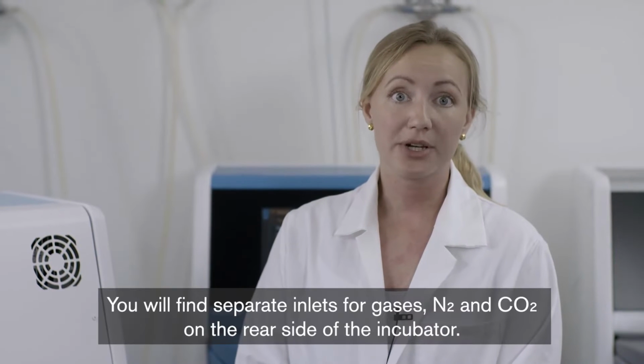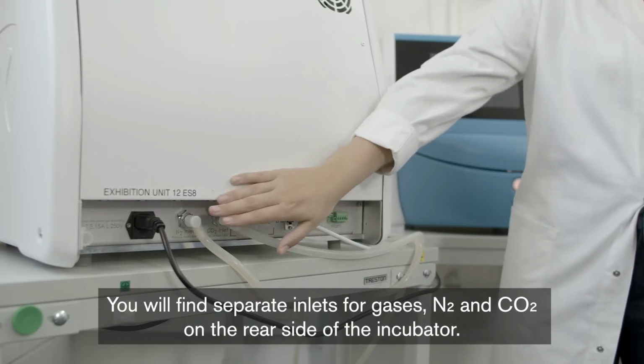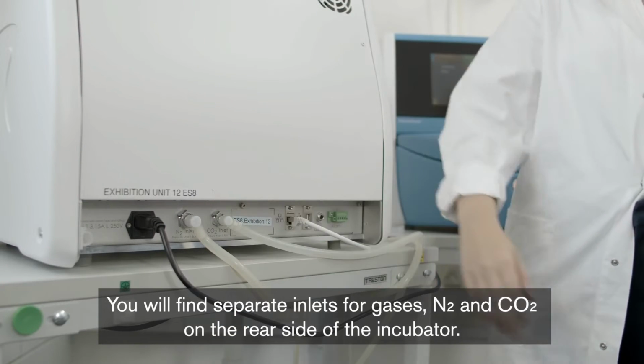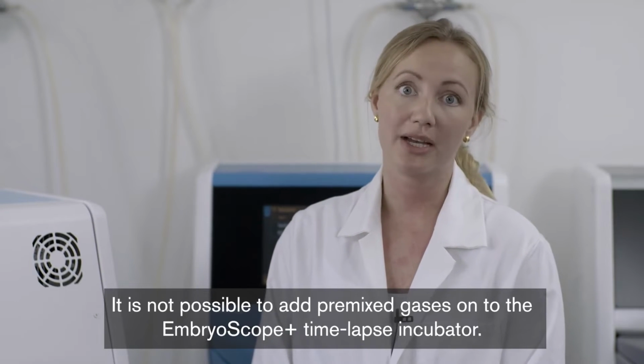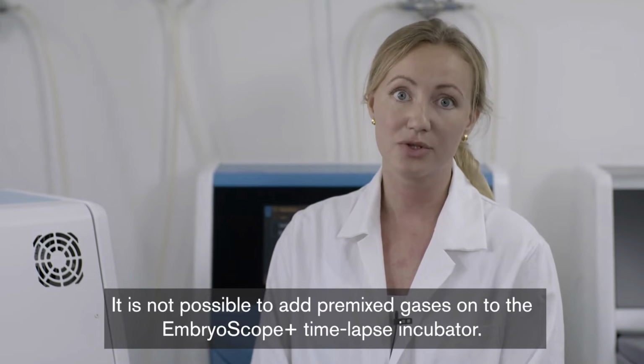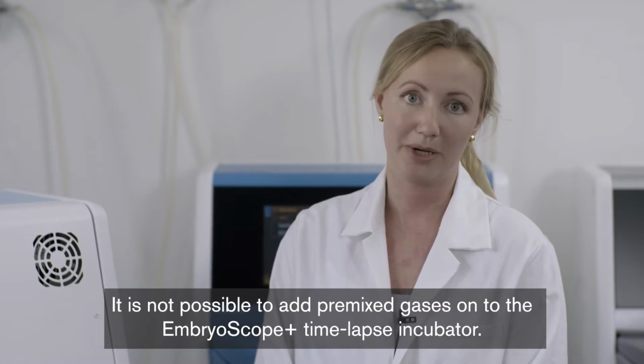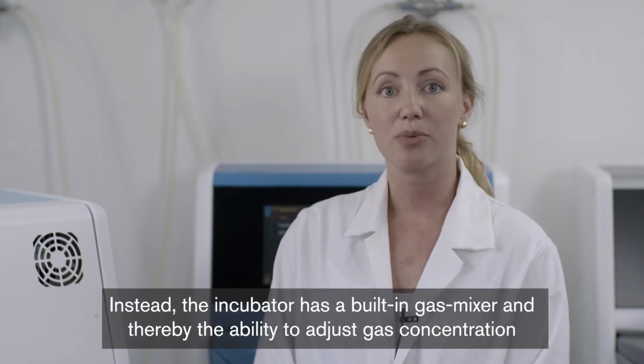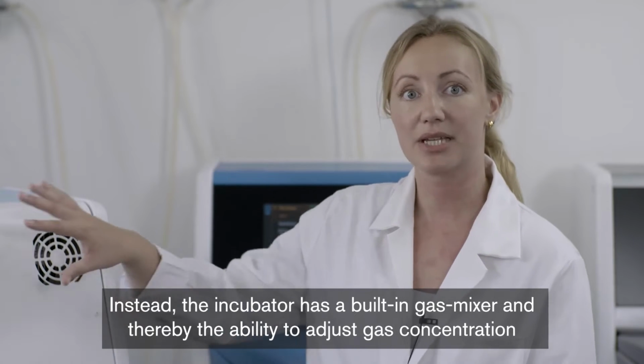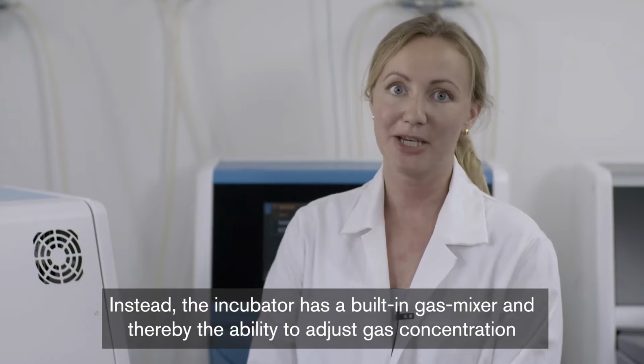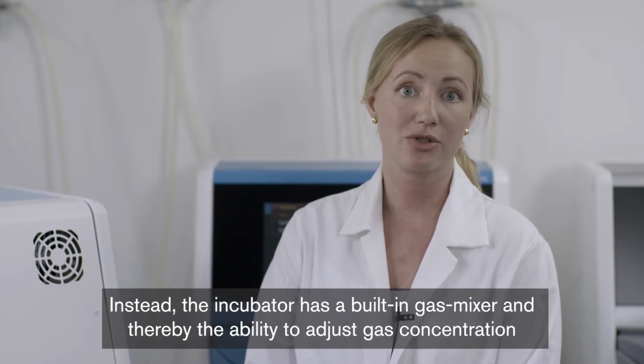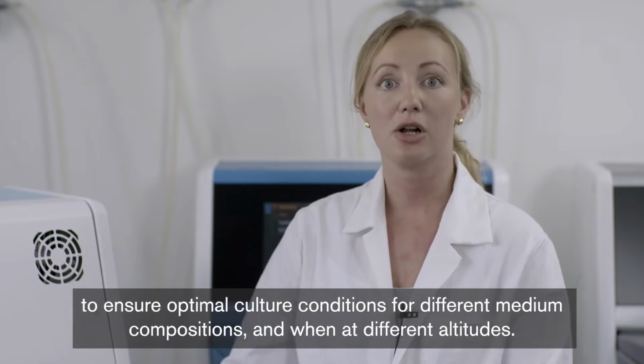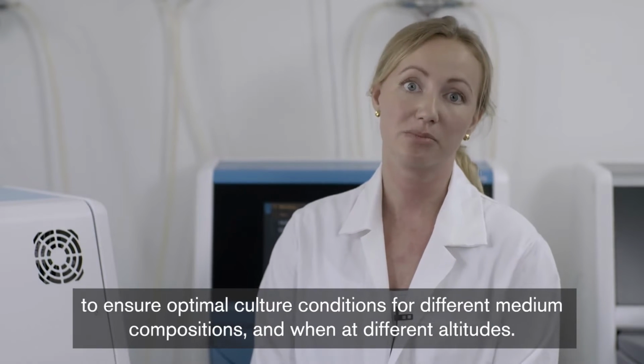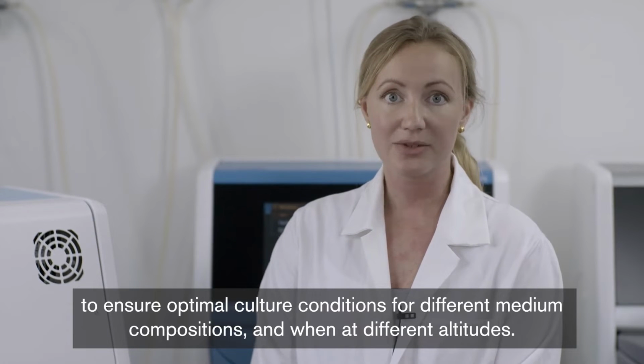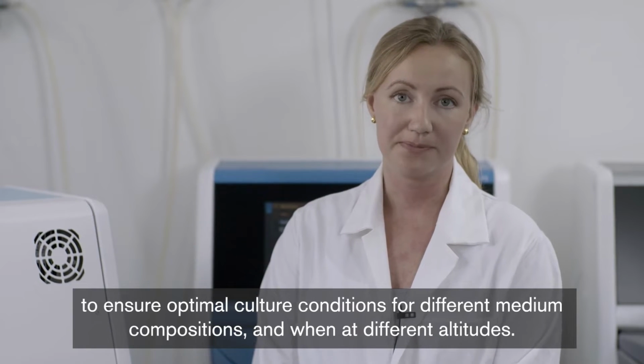You will find separate inlets for gases, nitrogen and CO2, on the rear side of the incubator. It is not possible to add pre-mixed gases to the EmbryoScope Plus time-lapse incubator. Instead, the incubator has a built-in gas mixer and thereby the ability to adjust gas concentrations to ensure optimal culture conditions for different medium compositions and when at a different altitude.